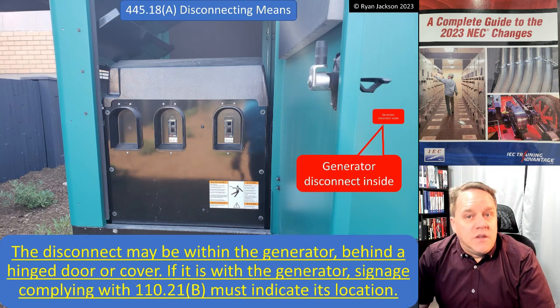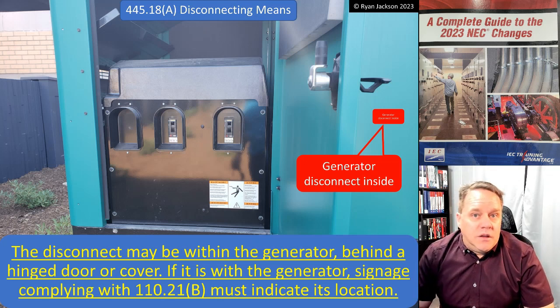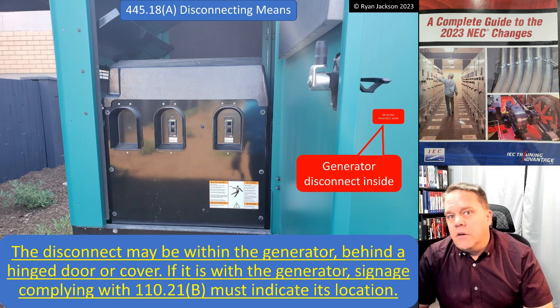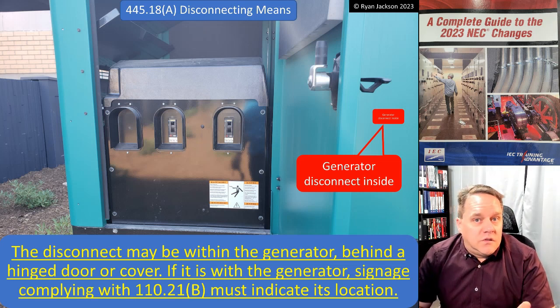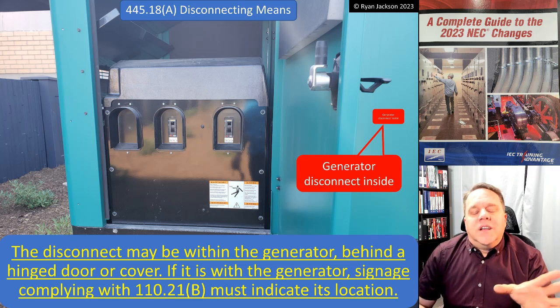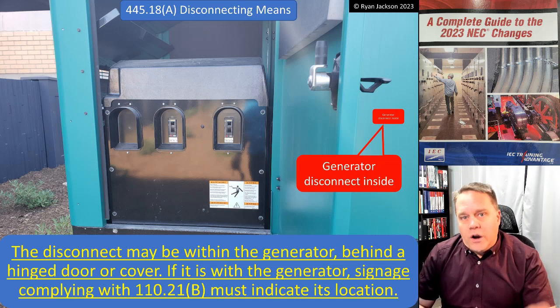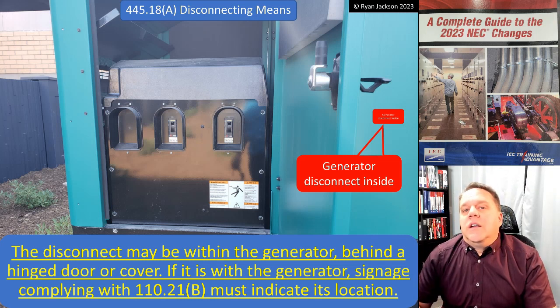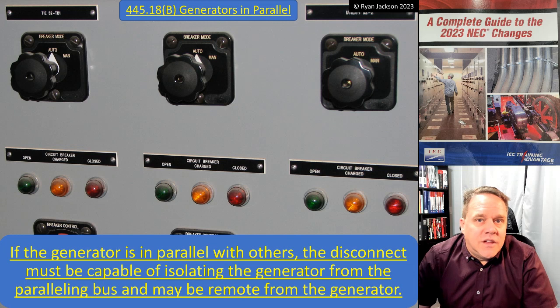The disconnecting means can be inside the generator, and oftentimes it is. It can also be inside behind a hinged door or a cover — a nice clarification, because a lot of people would say that doesn't comply, but absolutely it does. However, if the disconnect is inside the generator behind a hinged door, signage meeting the general signage requirements must indicate its location.